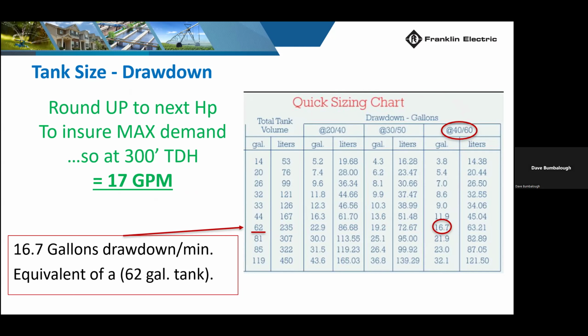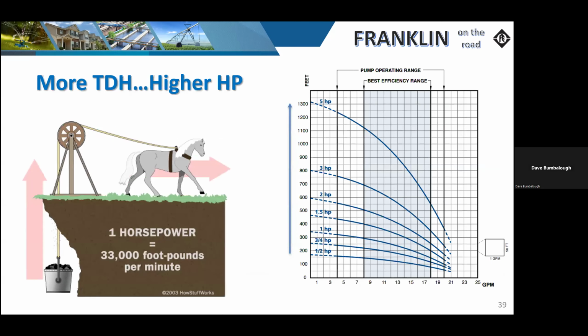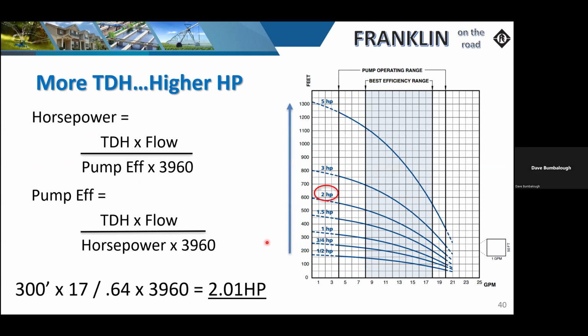And this is where I run into a lot of cycling issues. We often undersize the tank, and therefore you're going to cycle the pump and motor more than what the manufacturer recommends. So you've got to be very careful there. Now, as the TDH goes up, so does the horsepower. And of course, I put some formulas in here. I hardly ever use that, but that's how it calculates the horsepower. It's looking at, what are we lifting here? So that does come into the calculation, and there are formulas for it. The way you work this formula is your TDH times your flow divided by the pump efficiency, in which I've got to tell you, the pancake style are very puny.